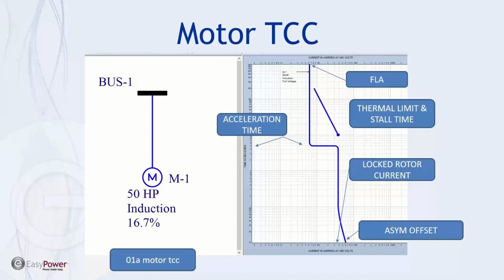Now, there's a tail that we refer to as the asymmetric offset, and it's very similar to Inrush, and it's based upon worst case. What we're plotting is worst case on the phase as we energize the motor and the current, and also we'll look at EasyPower and we'll see where this is set. But again, that needs to be accommodated when we're setting protective devices to differentiate between a normal start and an abnormal start. Any time current plot on the left side of the chart is considered a normal starting. Any time current plot to the right side of the chart would be considered an abnormal start, potentially abnormal start, and we would want to have protective devices that came into play.